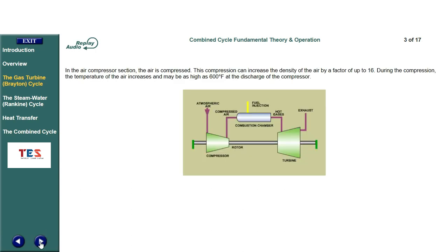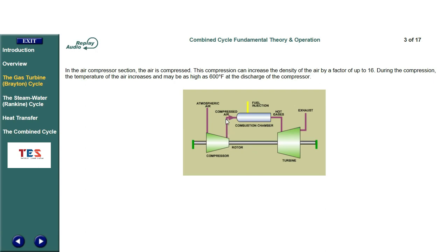In the air compressor section, the air is compressed. This compression can increase the density of the air by a factor of up to 16. During the compression, the temperature of the air increases and may be as high as 600 degrees Fahrenheit at the discharge of the compressor.